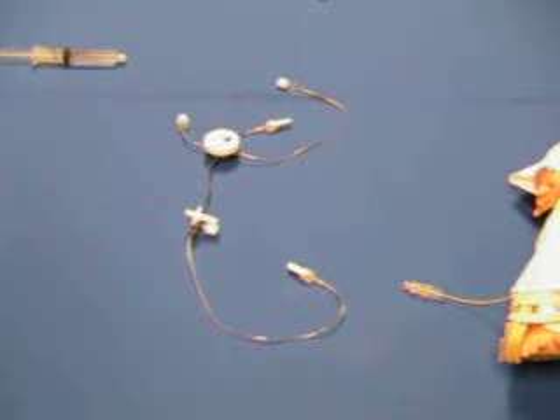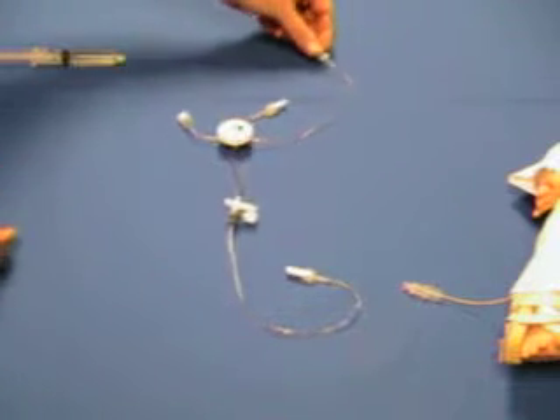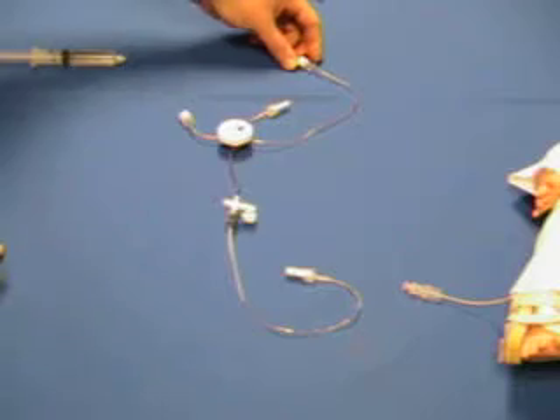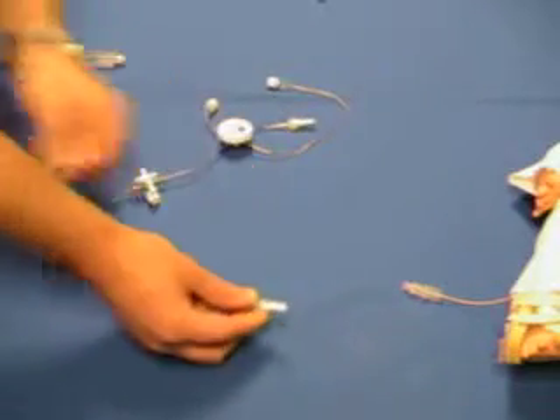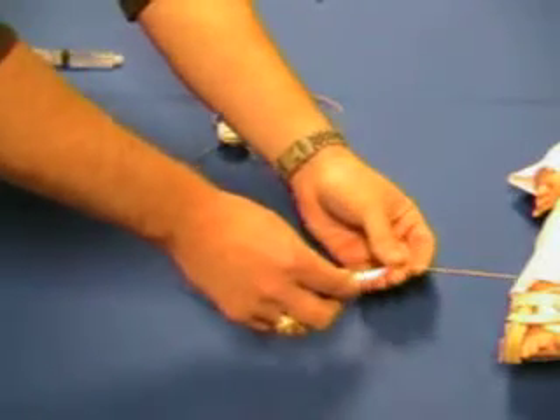This part of the VIA setup can be done at any time before the calibration, or during the calibration, during one of the 10-minute wait periods. This is the extension set. It's bag number 4 out of the sensor kit package. You've got your patient connection here. It's labeled patient. This is going to hook directly to the UAC with nothing in between it.